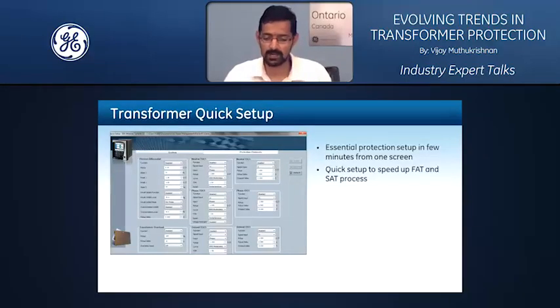So starting with a quick setup is a functionality. If you have a simple need to configure the core protection functions of the transformer, you can do it in minutes. If you are doing a factory acceptance testing or a site acceptance testing, you can quickly configure the device and start performing your testing in a very easy manner. That's the value behind this feature.